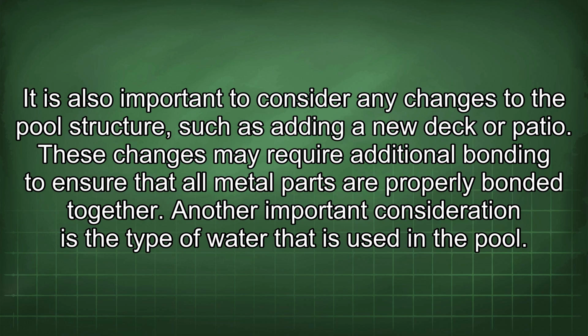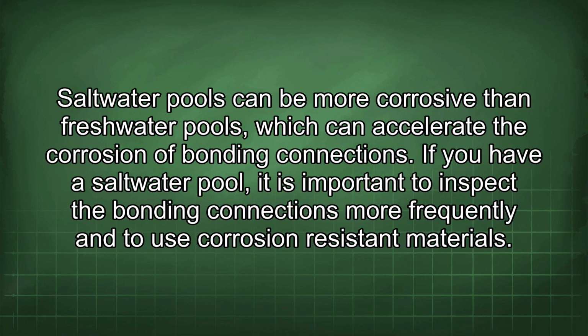Another important consideration is the type of water used in the pool. Saltwater pools can be more corrosive than freshwater pools, which can accelerate the corrosion of bonding connections. If you have a saltwater pool, it is important to inspect the bonding connections more frequently and to use corrosion-resistant materials.